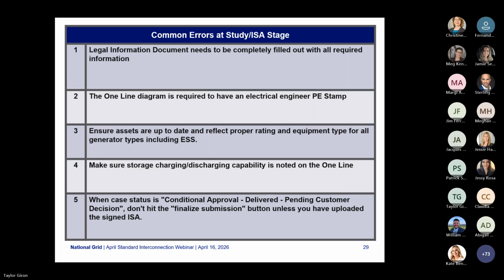Another error we see is with the PE stamps for the one-lines. Make sure the stamp follows the criteria requirements. For example, the symbol or image in the form of a rubber stamp, seal, or digitalized seal must contain the words Commonwealth of Massachusetts, the words professional engineer, and their name and registration number. It must be signed and dated with a legible handwritten signature adjacent to the seal, or a properly encrypted digital signature. When a digital signature is applied, it must have an electronic authentication document attached that is uniquely associated with the professional engineer and linked to the specific document in a manner that will invalidate the signature if any part of the document is changed. Lastly, the stamp should not be able to be copied or moved, and is not allowed to be used by another person.